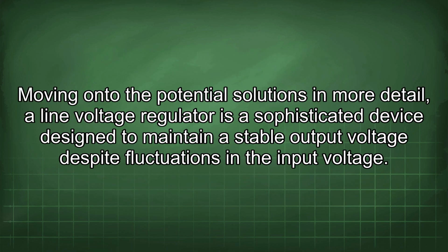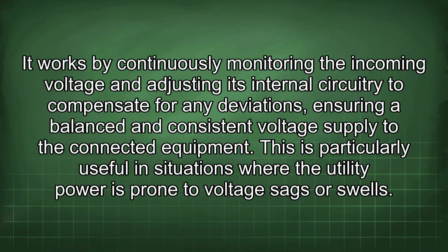Moving on to the potential solutions in more detail, a line voltage regulator is a sophisticated device designed to maintain a stable output voltage despite fluctuations in the input voltage. It works by continuously monitoring the incoming voltage and adjusting its internal circuitry to compensate for any deviations, ensuring a balanced and consistent voltage supply to the connected equipment. This is particularly useful in situations where the utility power is prone to voltage sags or swells.